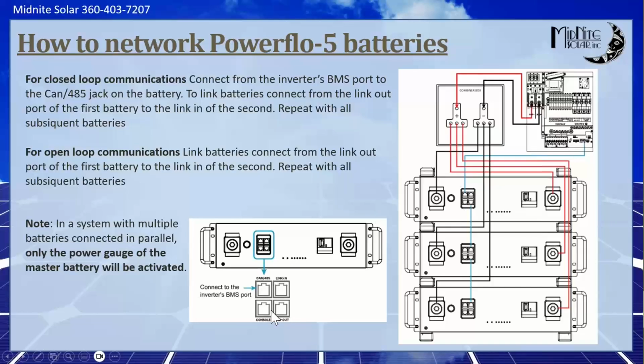Link in and link out: you go from the first battery's link out to the link in on battery 2, then out of battery 2 to in on battery 3. The system determines the master as the one with nothing plugged into the link in port. As you can see on this top battery, that link in port is empty, so the BMS automatically assigns that one as master, and everyone else becomes a slave to that battery.